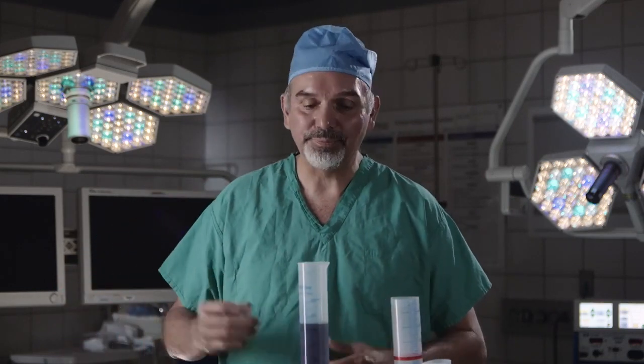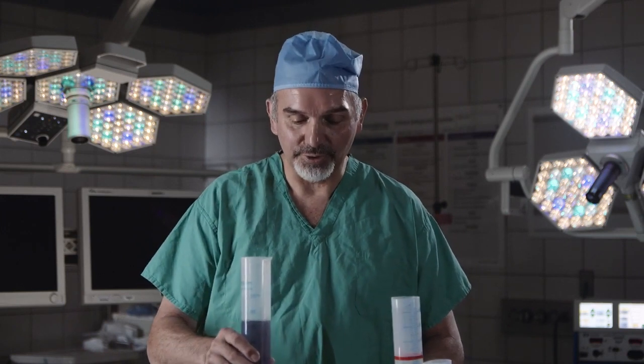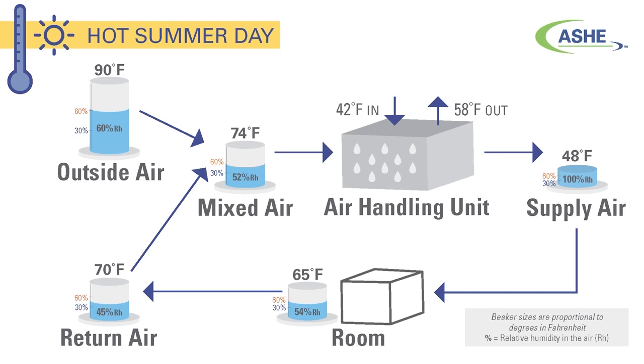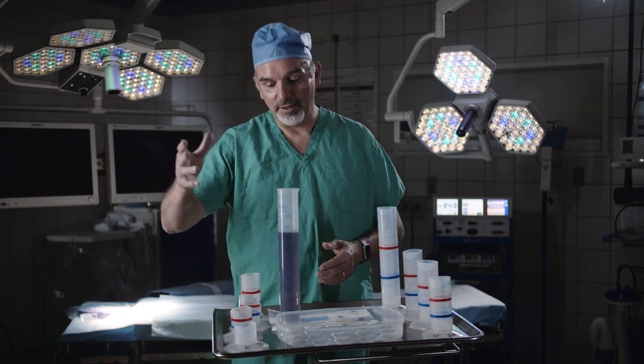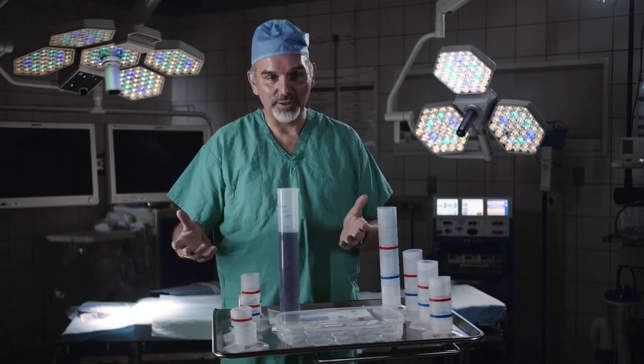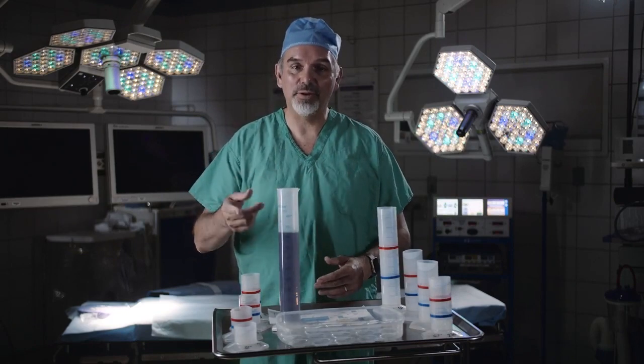Let's talk about the air handlers that serve this room. Looking at the hot summer day chart: we take about 20 percent of the outside air and 80 percent of air that's in this room, and we mix it together. We run it back through the air handler where it's chilled. There's a gigantic cooling coil in there that has 42-degree water entering that coil, and this air passes over it. When it comes out the other side, it'll be pretty much 48-degree air, and then it comes back into this room where it's heated from the lights and work, and returns back to cycle over again.